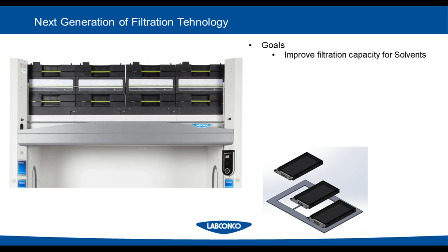Secondly, ease of integration and installation. This lower image here, where the 3 base modules are in descending order, they basically are - I have kids, you'll realize when I say this - like Legos. They interlock and they stack and they distribute power and communications both horizontally and vertically and self-configure. That was a huge step in the right direction for ease of integration and installation for our dealers, making sure that you, the customer, are handed over a fully working filtered fume hood.